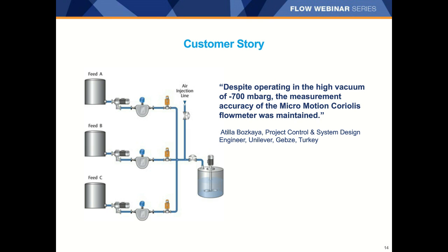Emerson's Micro Motion Elite Coriolis flow meters feature low-frequency flow sensors that improve flow accuracy in the presence of two-phase flow. A new digital transmitter also considerably improved the accuracy and stability of the signals from the flow sensor. Enhanced signal processing, as well as the sensor stability and design, ensured accurate measurements.